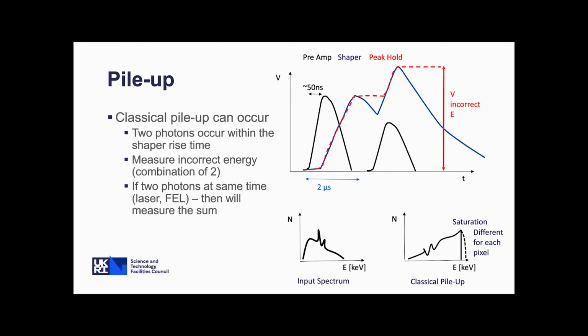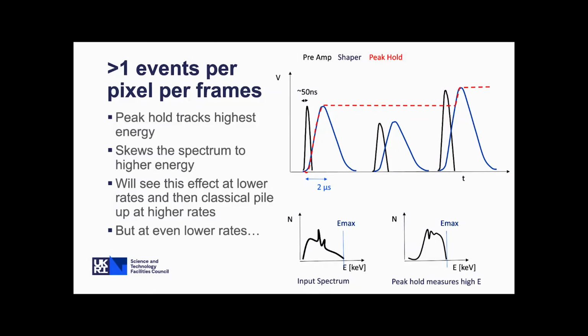So there are some of the artifacts that we can see in HEXITEC which are associated with the flux on the detector. If we have more than one event in a frame, then peak hold will always measure the highest energy event in that frame. So if you have too much flux on your detector, then what you're likely to do is start to bias the spectrum that you're reading towards the higher energies. Here we've got a case where we've got 3 events in a frame, and the peak hold is going to track that highest event and read out the highest energy.